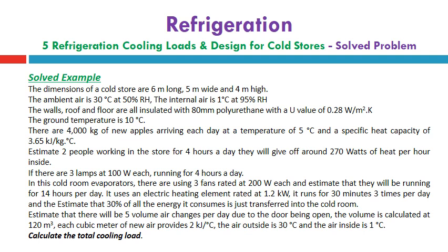There are 4,000 kilograms of new apples arriving each day at a temperature of 5 degrees Celsius, with a specific heat of 3.65 kilojoule per kilogram. Estimate 2 people working in the store for 4 hours a day. They will give off around 270 watt of heat per hour inside. There are 3 lamps at 100 watt each running for 4 hours a day, the same hours as the working persons inside the refrigerated store.